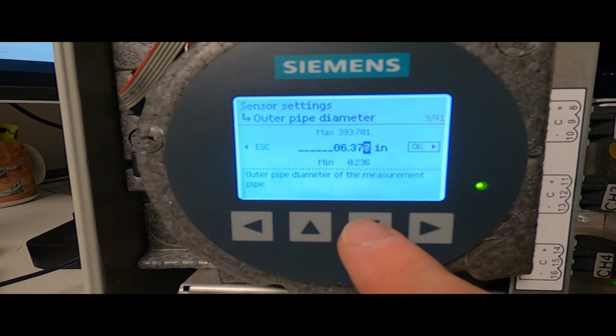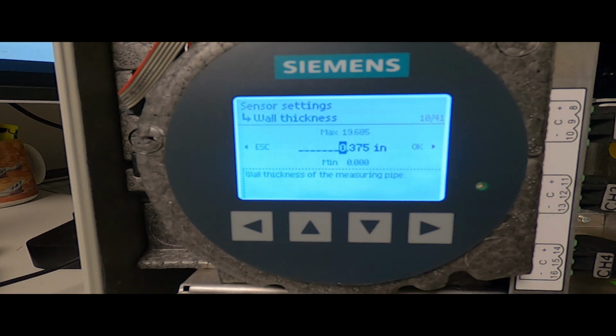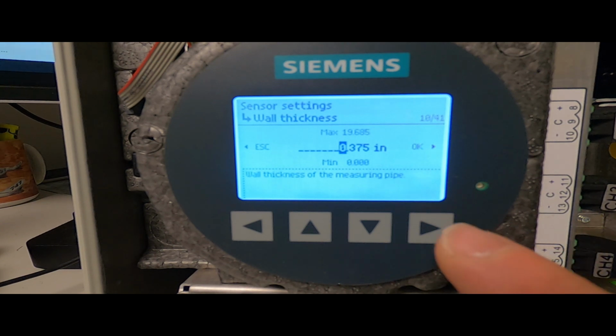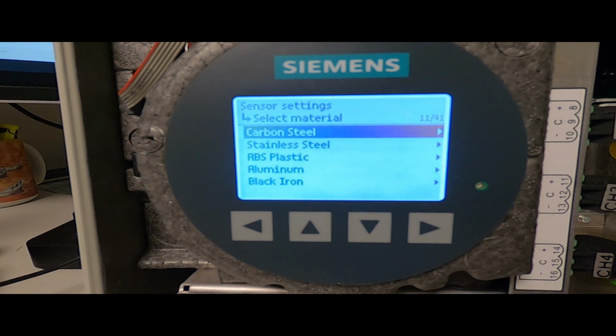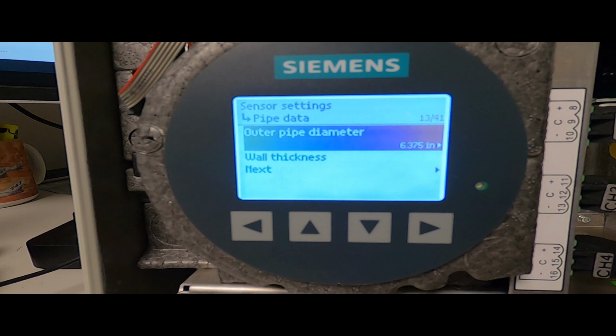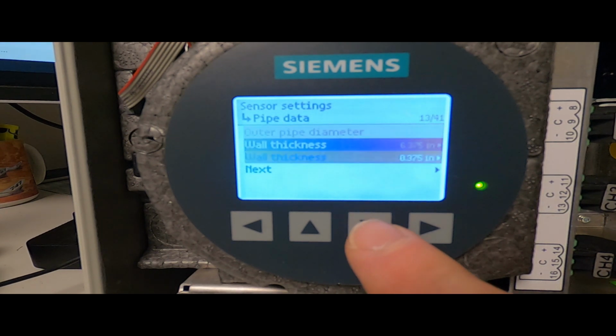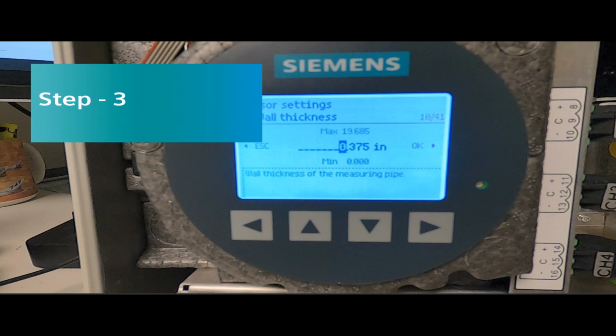Why, you ask? Well, on a smaller diameter, the sonic beam takes less time to travel. Thus the theoretical transit time is now much smaller. Remember, the goal is to make the flow meter expect the signal to arrive much earlier than normal. Step 3. Do not change the wall thickness. Well, that's easy.